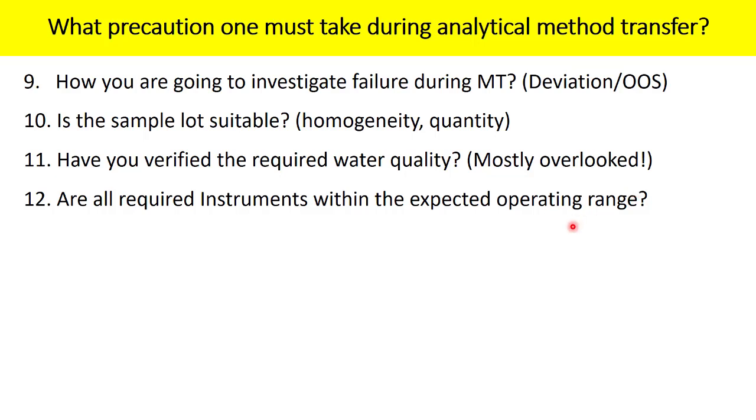Are all required instruments within the expected operating range? Now this is a very important point. Because most of the times we only think about, okay, there is a gas chromatograph required. I do have the gas chromatograph. But what specification is necessary for the gas chromatograph that is supposed to be used? Maybe in terms of your column oven temperature. Maybe in terms of the heating range of the detector. Maybe in terms of your injection volume. Those details have to be confirmed well before you start your experimentation.